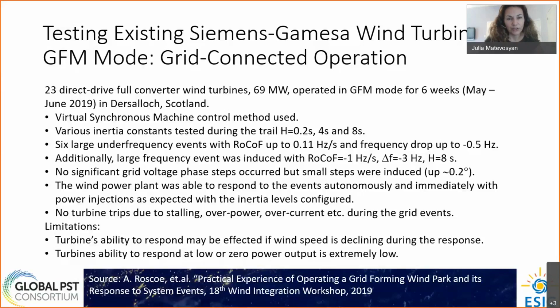When I'm saying virtual inertia here, I would like to mention that it is using kinetic energy of rotating wind turbines. This is different from what's been termed as synthetic inertia, since this is not requiring any external frequency measurement. So when the inverter is operating in grid forming mode, it behaves like a virtual synchronous machine, and it uses energy from the rotating mass of wind turbines as energy storage or energy buffer.